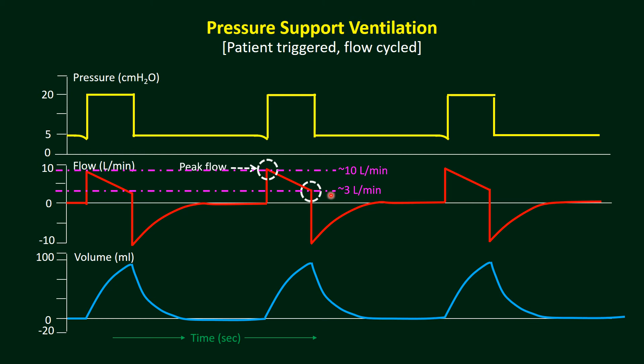So this is the first example. Flow cycle is set to 10. So this is the peak flow, maximum flow, 100% of flow, and as the inspiration goes on over time, flow is going down, flow is getting reduced, and when flow comes to 10% of maximum flow here, then inspiration ended and expiration started. Here flow cycle is set to 25%. So after maximum flow, flow is getting reduced, decelerating, and when it comes to 25% of the maximum flow, then inspiration ended and expiration started.